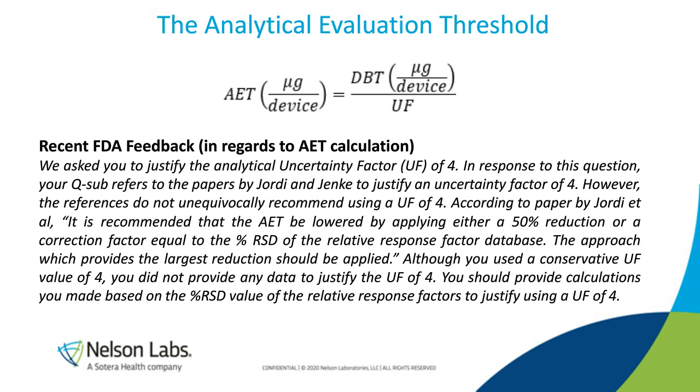This threshold is super important. Be ready to defend what this analytical evaluation threshold is and how you got to that specific number. The wisest thing to do would be to do that up front, probably in your pre-sub. If you don't go through the pre-sub process, then I would for sure make sure it's included in your chemistry reports and in your toxicological risk assessments to avoid getting kicked back on this point.